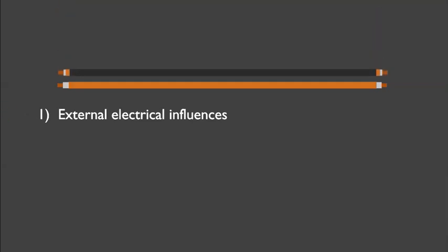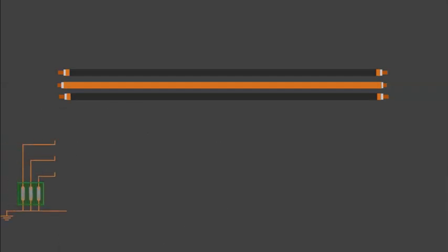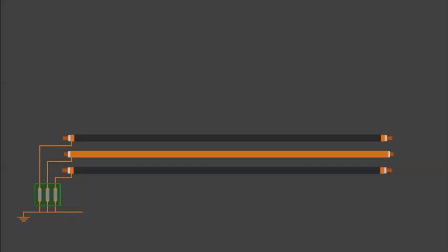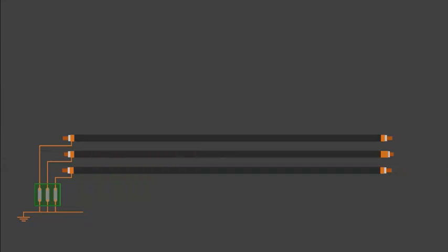This metallic sheath serves two main purposes. The first one is it protects the cable from external electrical influences. Actually, where the cable is buried or placed, in the surroundings there may be other cables of the same circuit or different circuits. Due to the influence of current through the different circuits or different phases of the same circuits, there may be electrical interference in the conductor of the cable. If this metallic sheath is properly earthed, then this will behave as an electrical shield over the conductor.